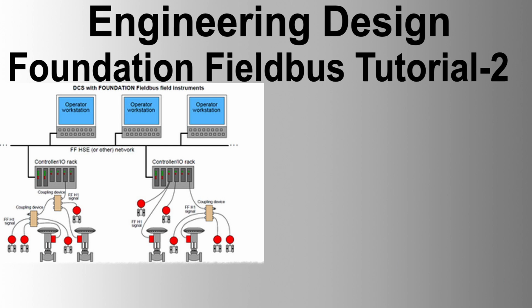AO block. The analog output AO block is designed to allow users to enjoy a standard model of output devices like a valve positioner. An AO block receives the control value from a control block and sends back the current control value so that the control block can calculate the next control value or track the current value if the AO block is not controlled by that control block.